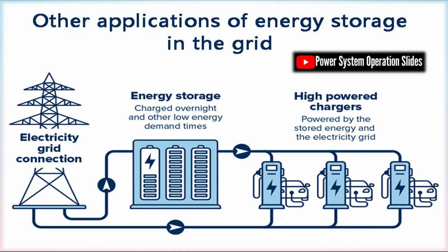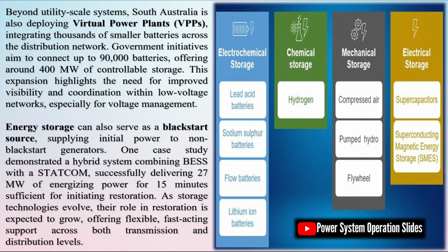Energy storage can also serve as a black start source, supplying initial power to non-black start generators. One case study demonstrated a hybrid system combining BESS with a STATCOM, successfully delivering 27 megawatts of energizing power for 15 minutes, sufficient for initiating restoration. As storage technologies evolve, their role in restoration is expected to grow, offering flexible, fast-acting support across both transmission and distribution levels. WAMS in power system restoration.